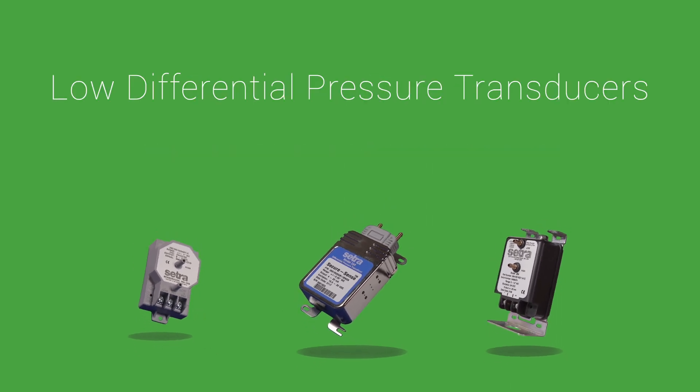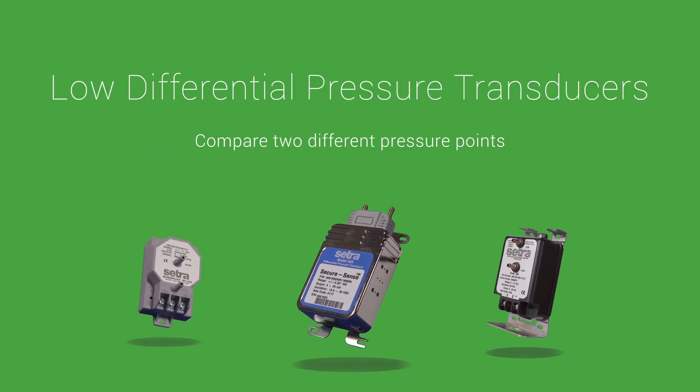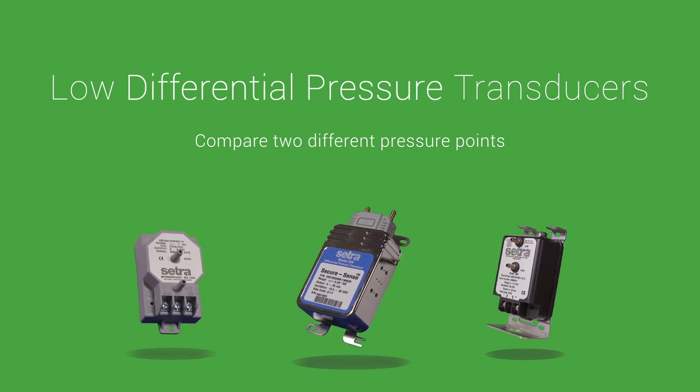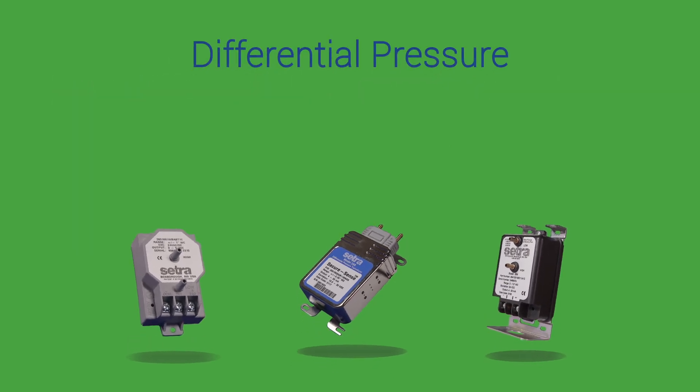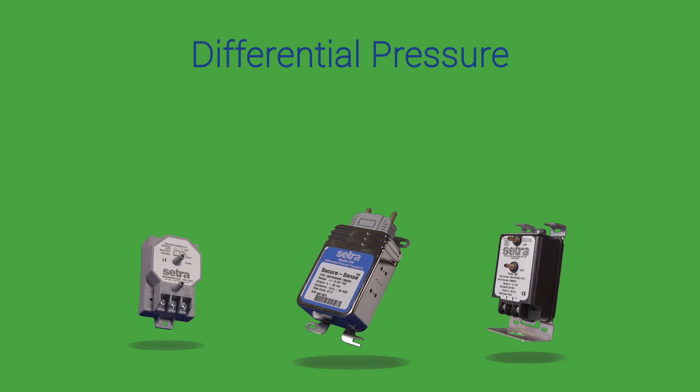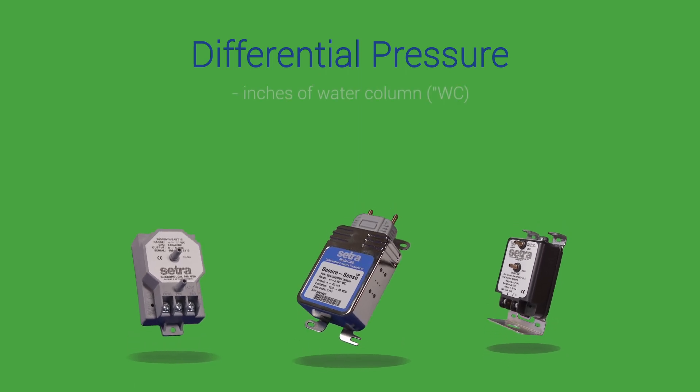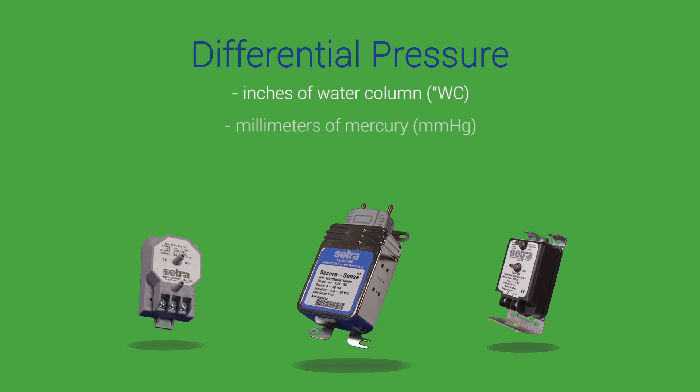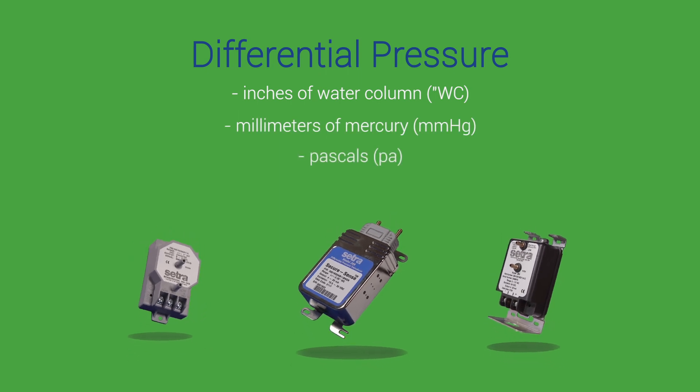Differential pressure transducers compare the pressure in one space to the pressure in another space. The difference between the two spaces is called the differential pressure. Low differential pressure is typically expressed in inches of water column, millimeters of mercury, or pascals.